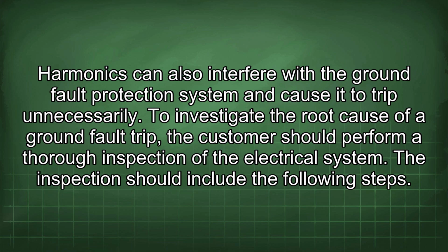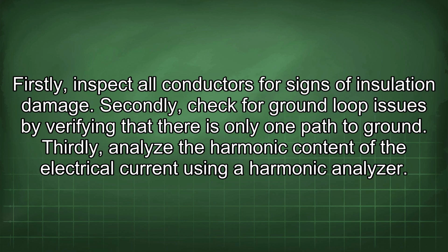To investigate the root cause of a ground fault trip, the customer should perform a thorough inspection of the electrical system. The inspection should include the following steps. Firstly, inspect all conductors for signs of insulation damage. Secondly, check for ground loop issues by verifying that there is only one path to ground. Thirdly, analyze the harmonic content of the electrical current using a harmonic analyzer.